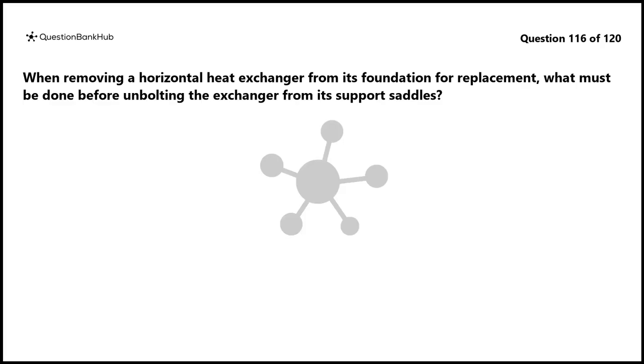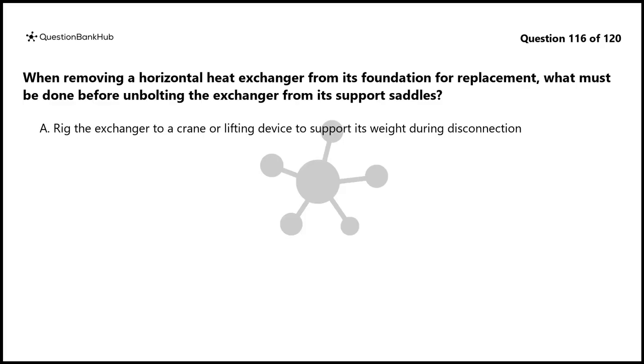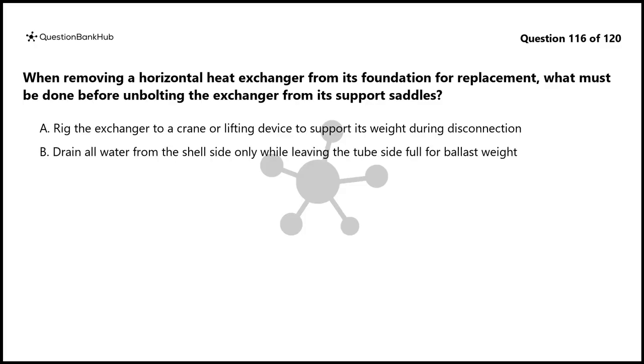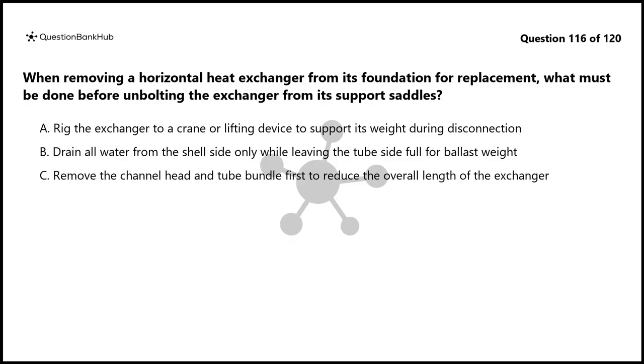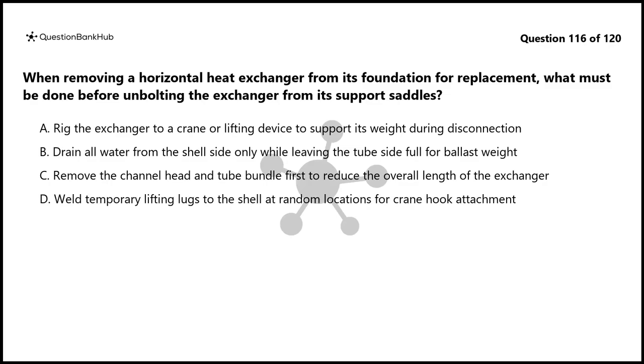Question 116. When removing a horizontal heat exchanger from its foundation for replacement, what must be done before unbolting the exchanger from its support saddles? A. Rig the exchanger to a crane or lifting device to support its weight during disconnection. B. Drain all water from the shell side only while leaving the tube side full for ballast weight. C. Remove the channel head and tube bundle first to reduce the overall length of the exchanger. D. Weld temporary lifting lugs to the shell at random locations for crane hook attachment.